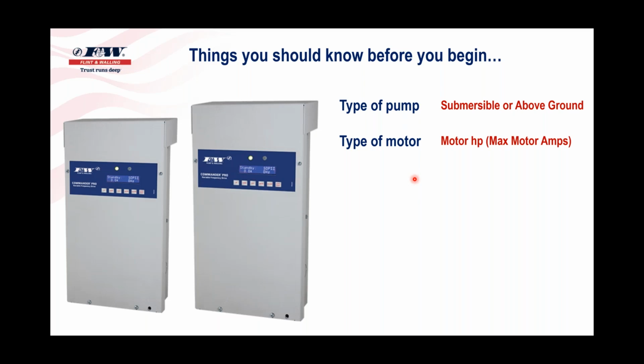And when we do that, we express that horsepower in a little different term. It doesn't come right out and ask what horsepower. It asks, what is the max motor amps? Knowing what those max motor amps are for any given horsepower motor is going to facilitate the initial programming here, because not all motors that this drive could be subject to running, whether it's a Pentek or a Franklin or our own, necessarily all have the same max motor amps ratings. So we want to look at that max motor amps, because that's what we're going to tell the drive what motor horsepower it's going to operate. I'm going to circle back on that in a little bit.